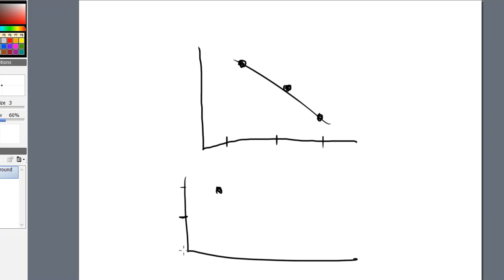And the reason that I'm drawing the calibration curve kind of backward is because that's exactly how the readouts are going to be. So when I place the probe in pH buffer 7, 7 has a reading of 0 millivolts, all right? So 0 millivolts, that's going to be the reading of pH of 7. And here on the graph, I've marked the 0, and we can go above, positive, and we can go below, and that's negative. If I put the pH probe in buffer of 4, what will happen is that this will often be like 180 millivolts, give or take a little bit. And that 180 millivolts will be a positive value at pH of 4.